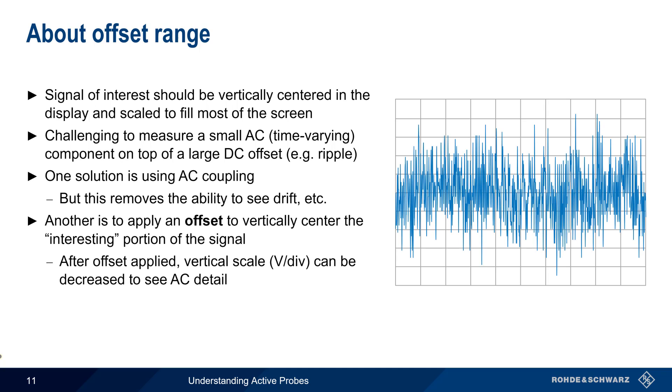Another approach is to apply an offset to the channel so as to vertically center the signal. After this offset has been applied and the signal has been moved to the center of the display, the volts per division setting can be decreased to see the AC component of the signal in more detail.